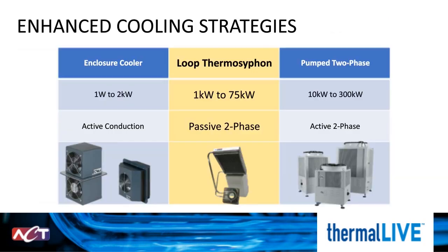Two-phase heat transfer is used in many other power electronic systems as well that don't always require that completely sealed solution. These applications can leverage a loop thermosiphon, which has the capacity to remove up to 75 kilowatts of waste heat.